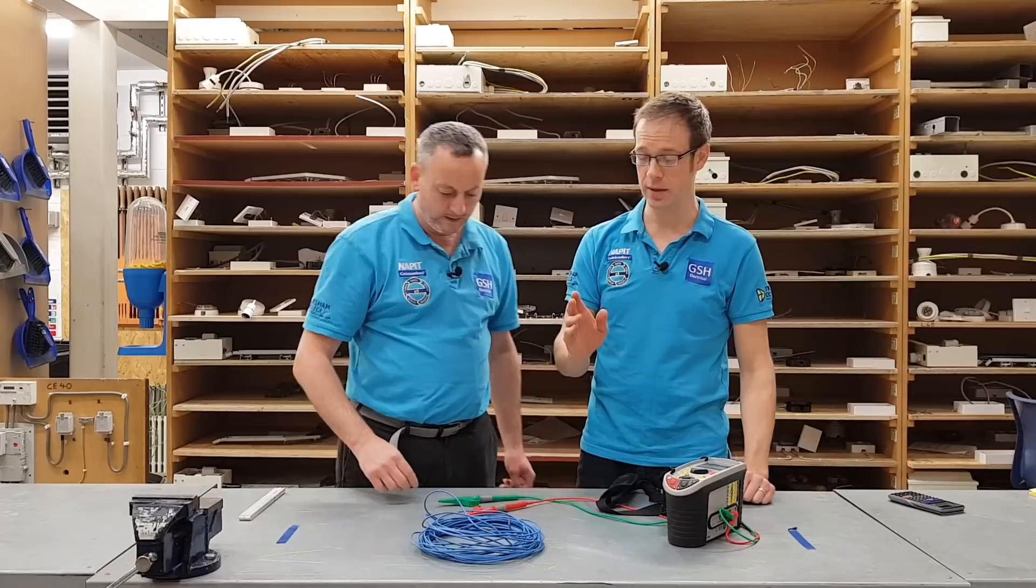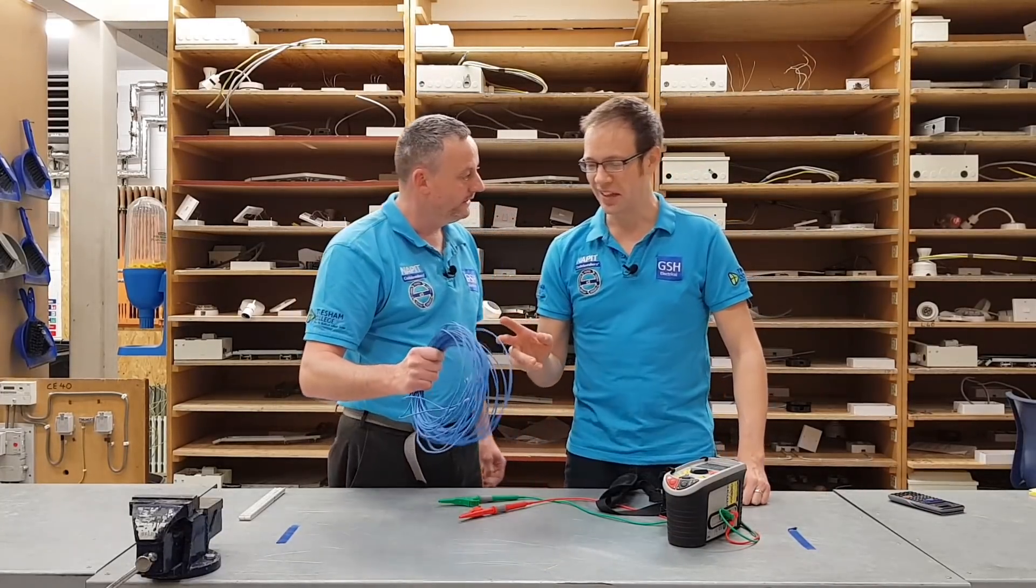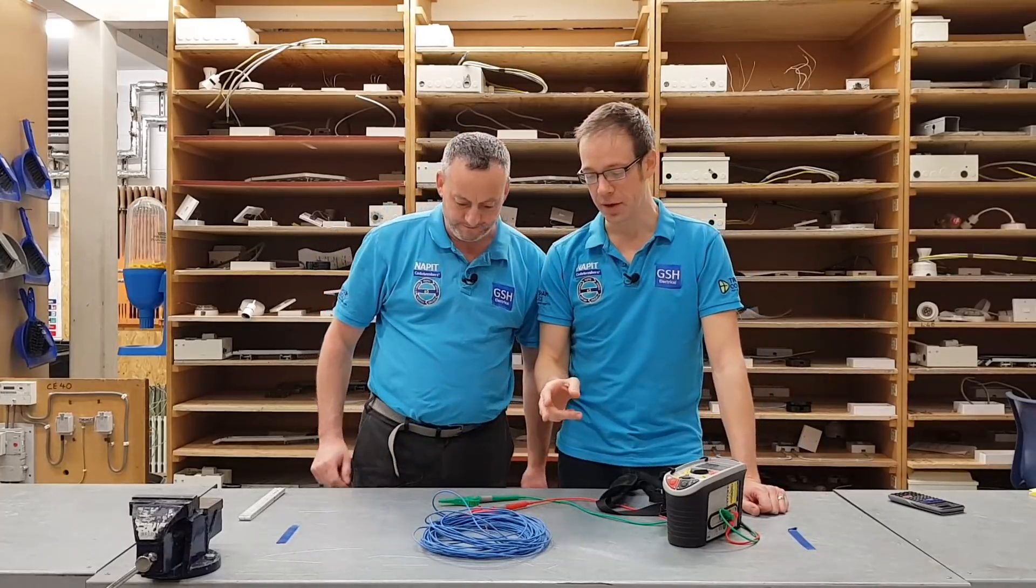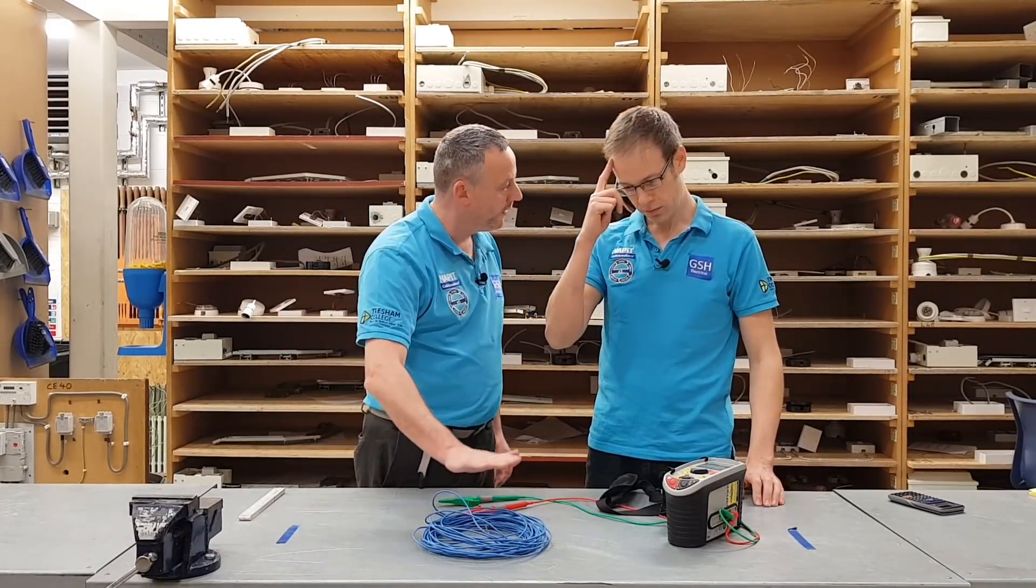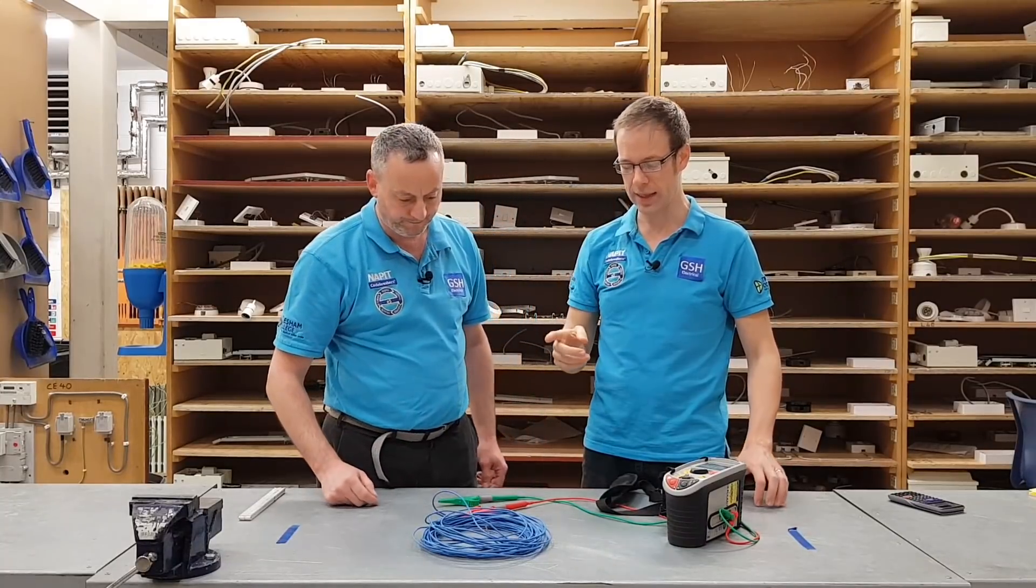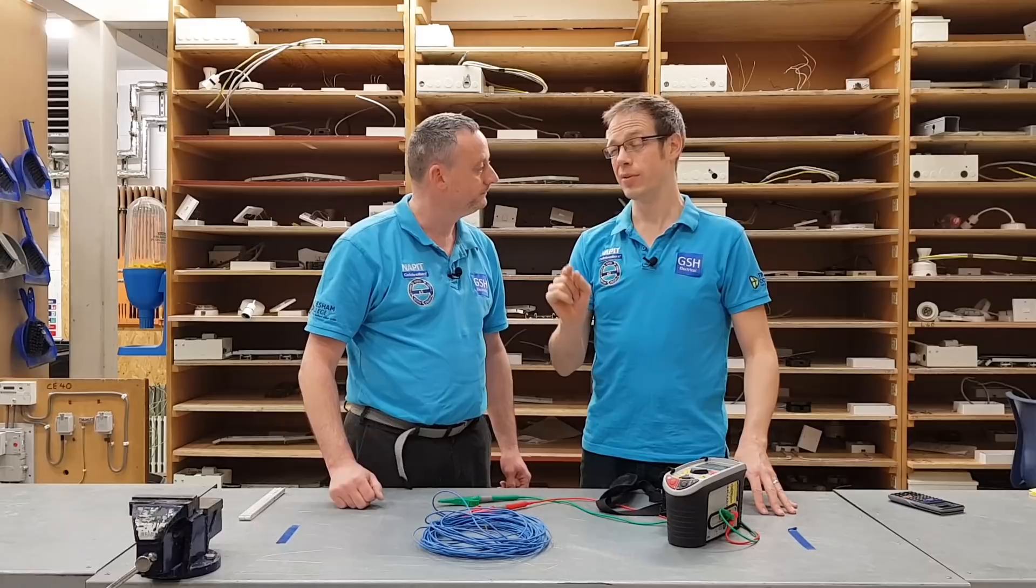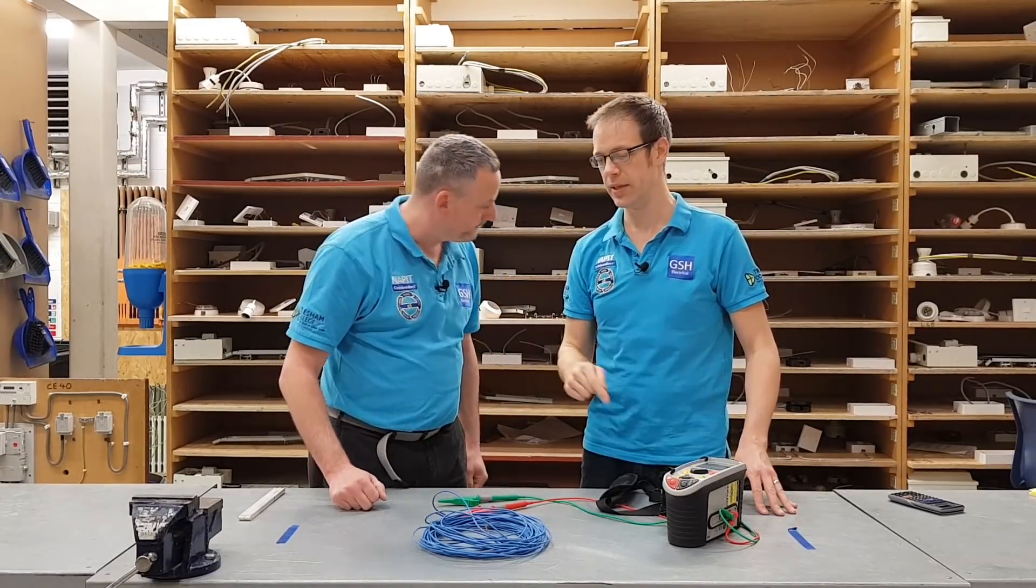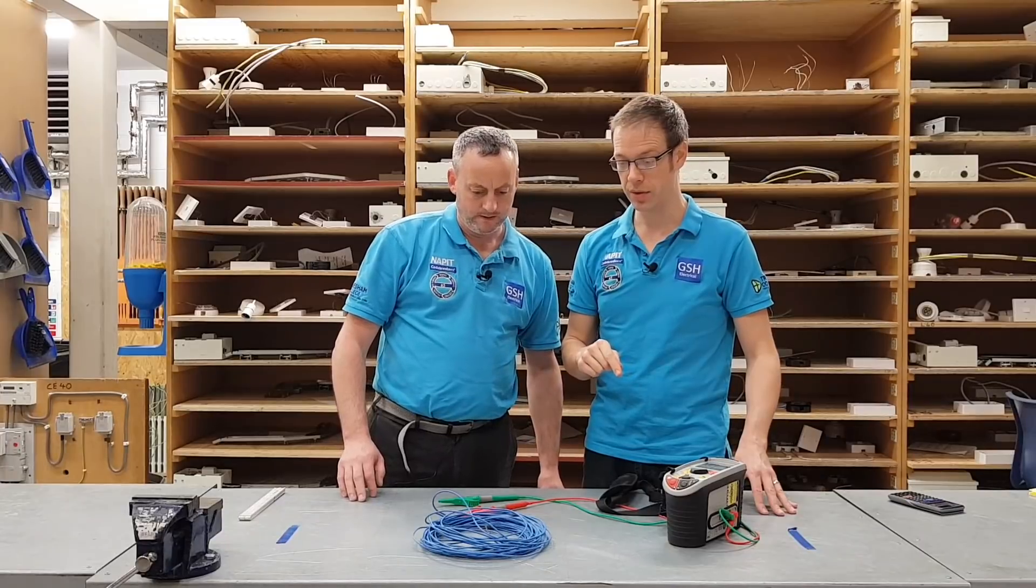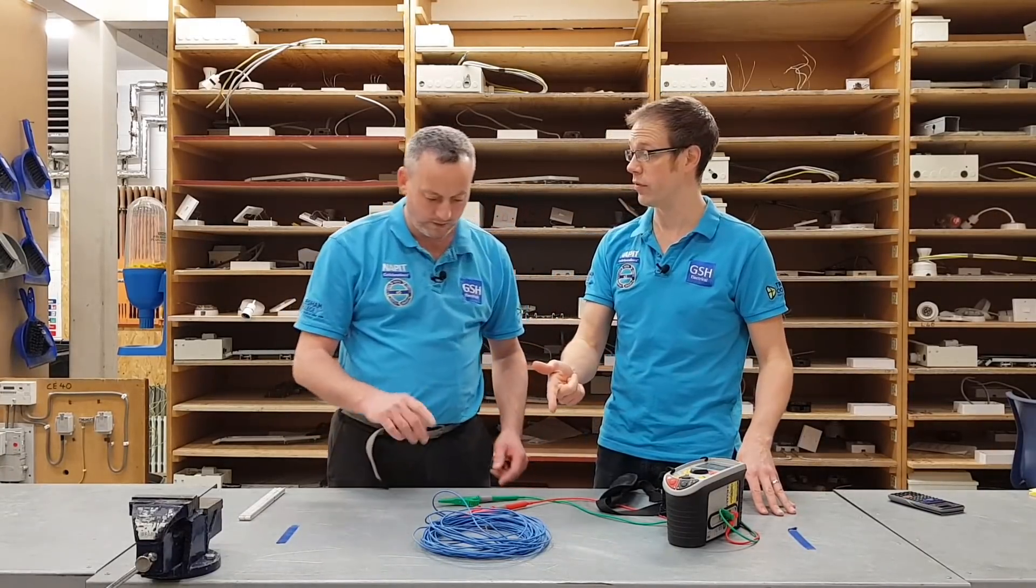All right, I like the sound of that. So there's a few things we need to know about the conductor before we start doing this. I'll get it out of the bin. What I need to know is what is the cross-sectional area of the cable? It's 1.5 millimeter squared. And is it a copper cable? It is, yeah, copper material. So we'll need the resistivity of copper which is 17.2 micro ohm millimetres. And I'll also need to know the resistance of the conductor.